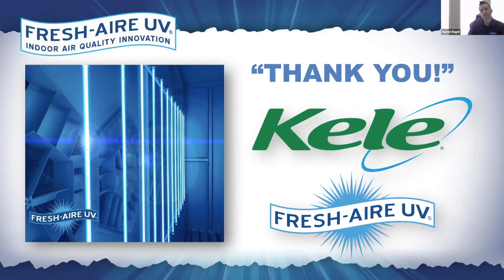Great. Jason asks, will UVC penetrate an 8 to 10 row CW coil in reference to cleaning coils? Well, it depends on the depth of the coil. With UV light, time is the overriding factor here. Typically, if you go over 10 to 13 inches, let's say a 13 inch coil, you'd probably want to put a lamp on the other side, not necessarily as many lamps as you would have on one side, but to complement what is happening on the other side. But location is really strategic. That's why we try to promote mounting a UV system on the downstream side of the coil.